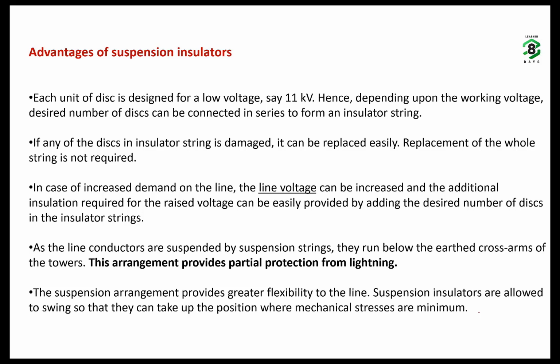Each unit of disk is designed for a low voltage, say 11 kV. Hence, depending upon the working voltage, the desired number of disks can be connected in series to form an insulating string. So let us suppose that each disk can handle 11 kV. So we can easily provide insulation for higher or lower voltages by adding disks in series.